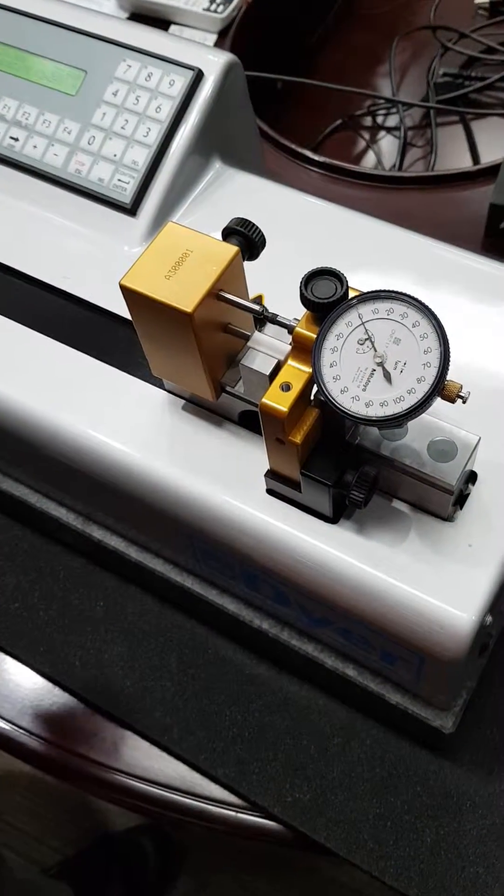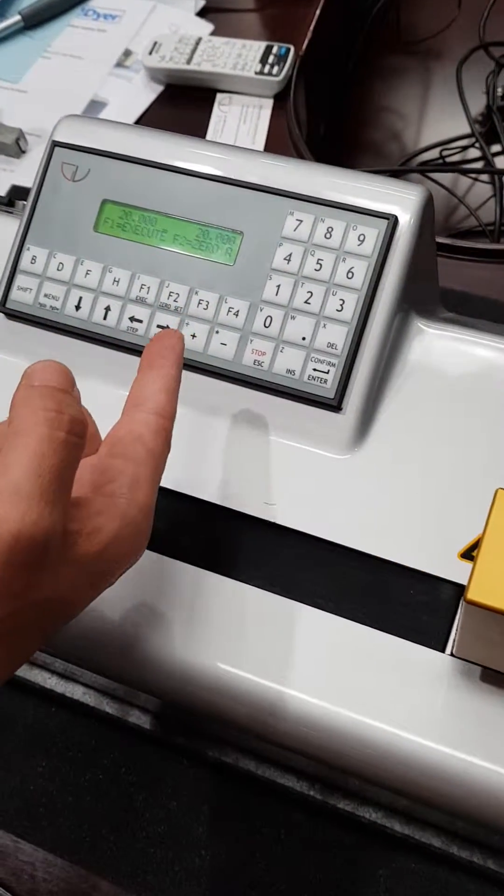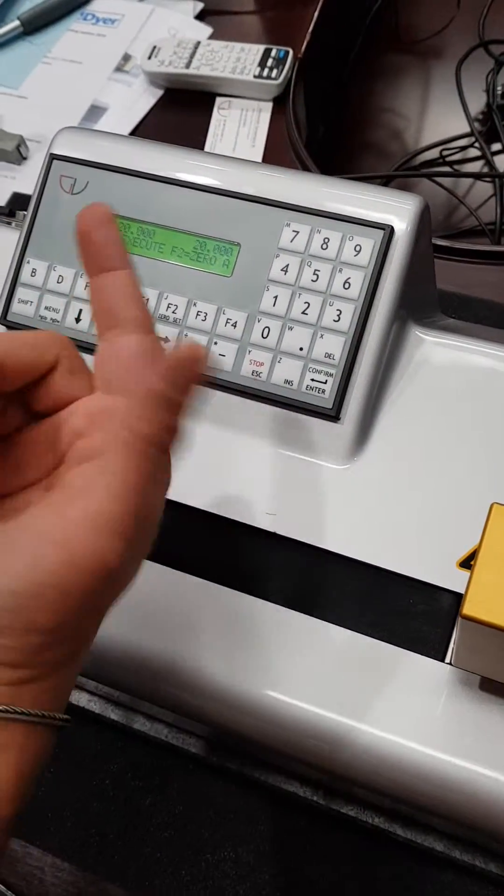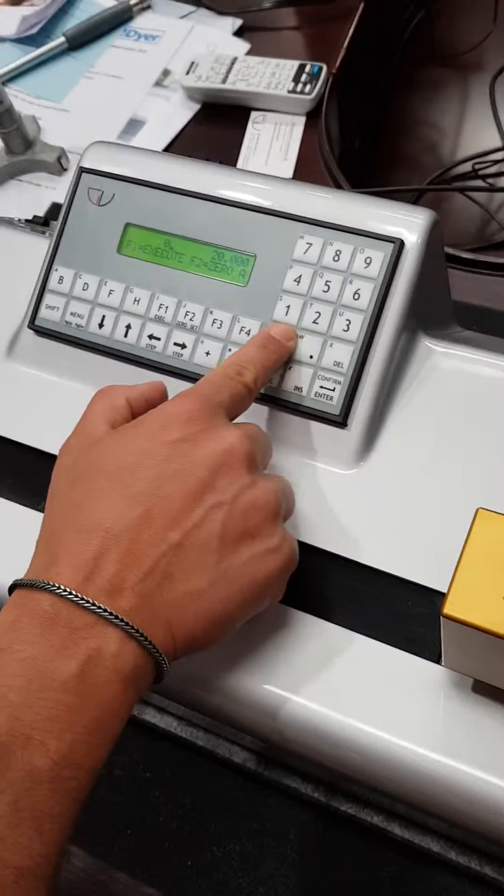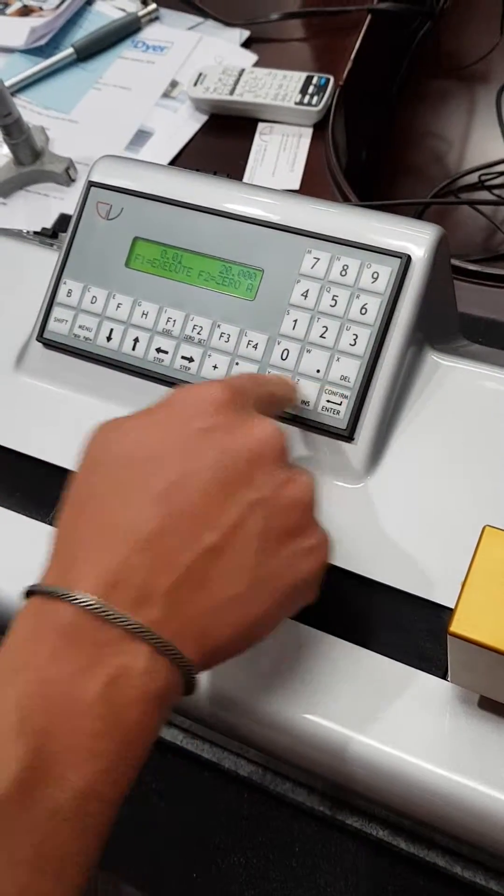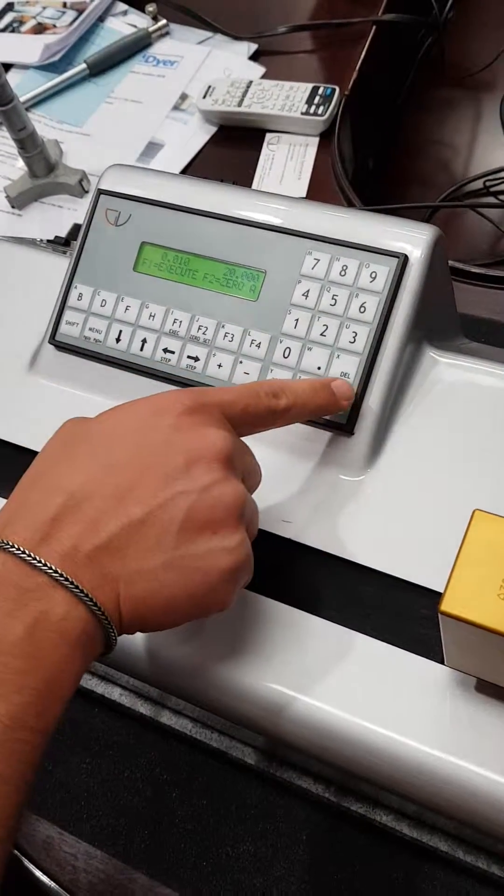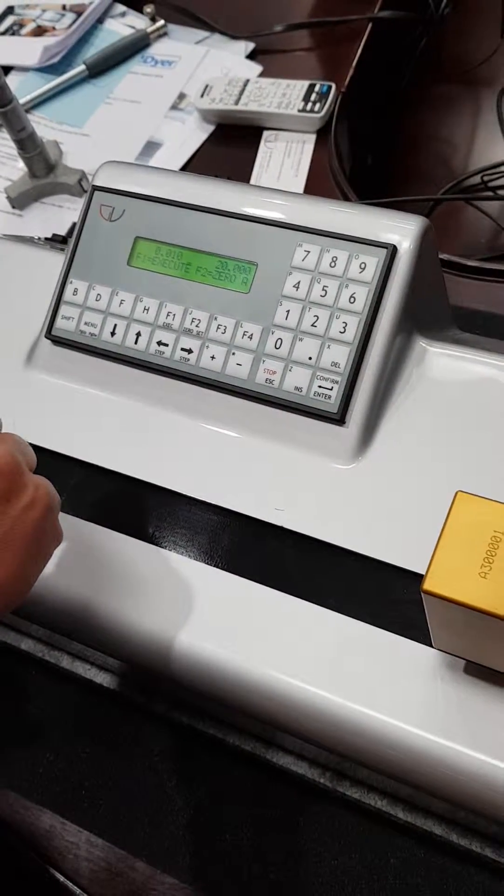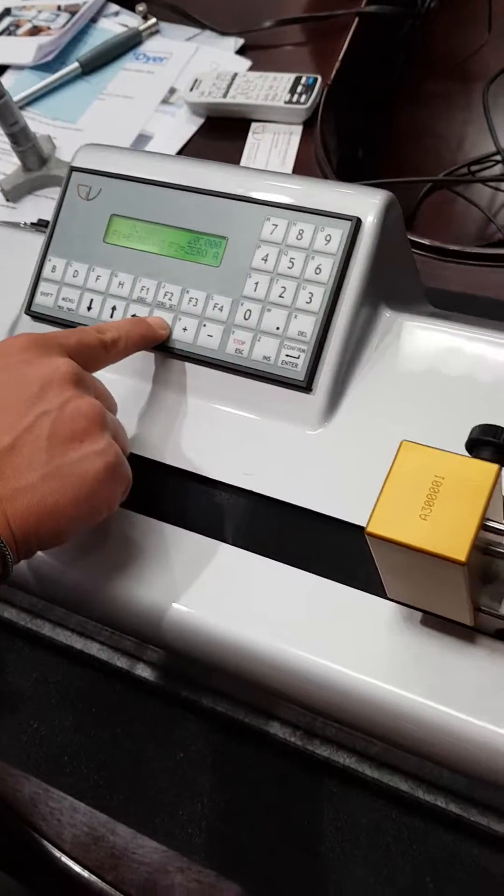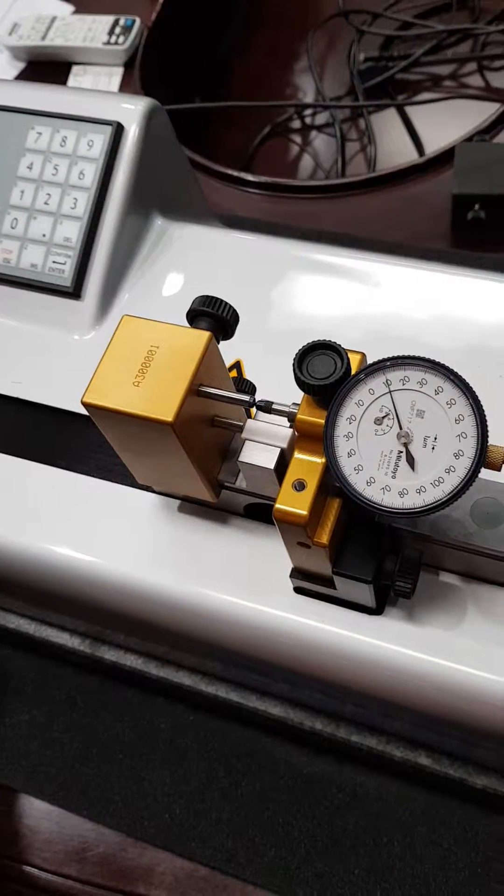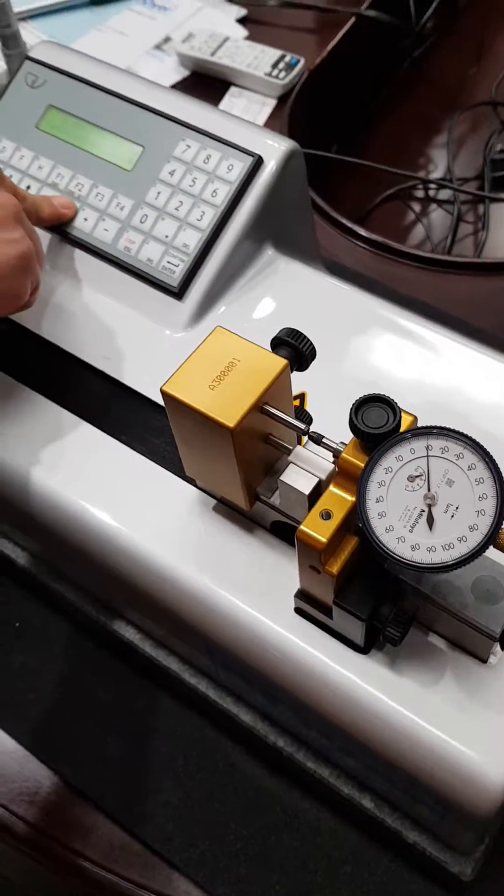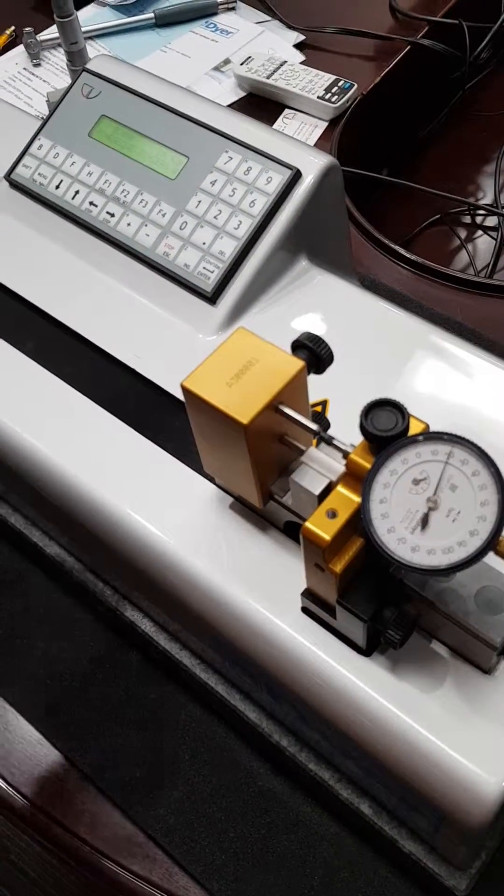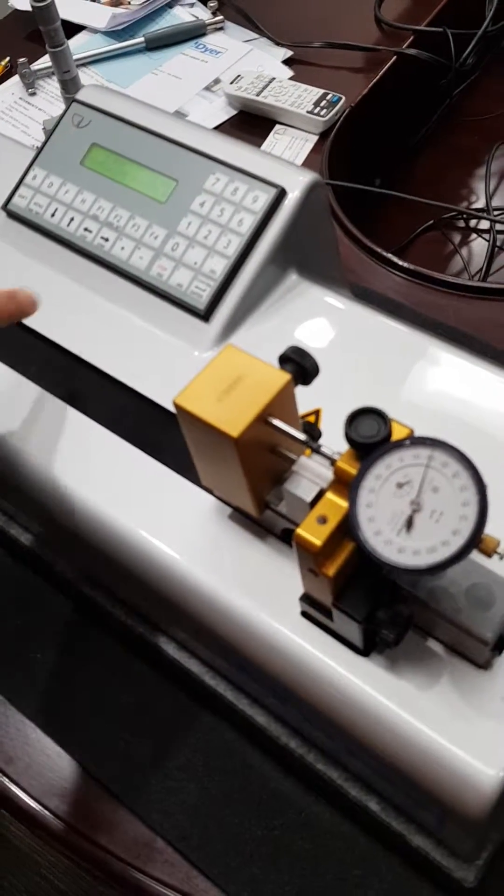Let's proceed with the manual steps. Let's decide to have about a 10 micron step. I confirm with enter, and now with the two arrows I'm going to move. Each time I press the button, the machine is going to move by 10 microns.